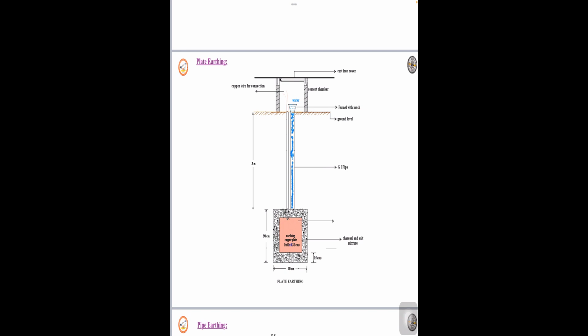Now when we observe how it works, in an earthing system the metallic body, whether it may be a plate or pipe, which is embedded in the earth is called the earth electrode. For effective earthing, the resistance offered by the earth electrode along with the soil in which it is embedded should be quite low, as we saw in the definition. The copper plate is the best choice. Why? It is least affected by the moisture content present under the earth, and it will not rust easily.